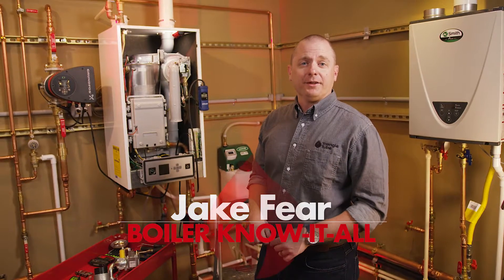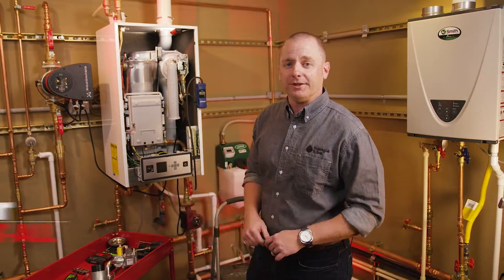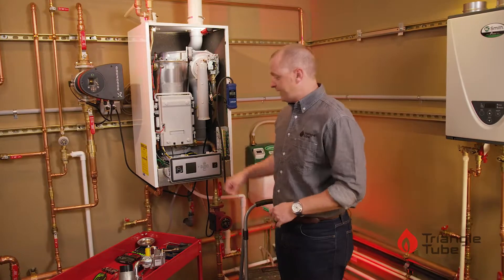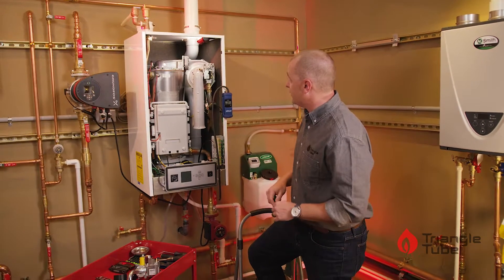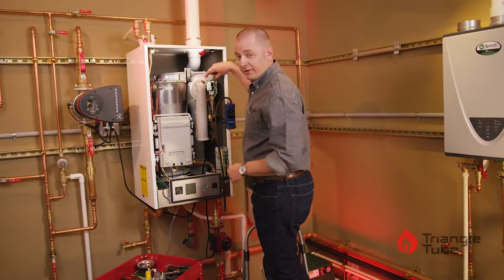Hi, I'm Jake Fear from TM Sales, here with Triangle Tube to show you how to check the gas pressure on a PA series boiler. As always, make sure the power of the unit is off as well as the gas on a PA 175 or 250 series, which is what we have here in front of us. We'll locate the gas valve.